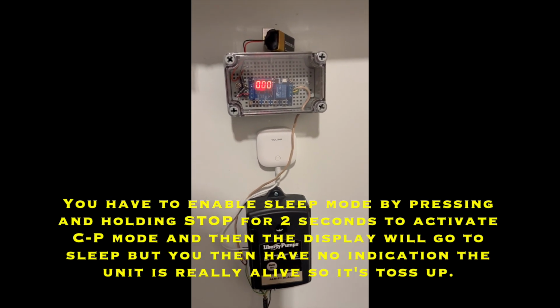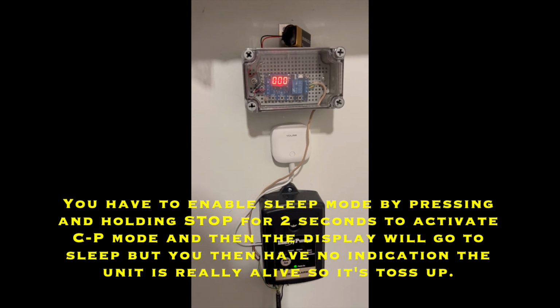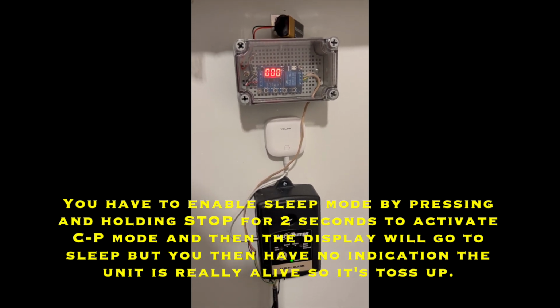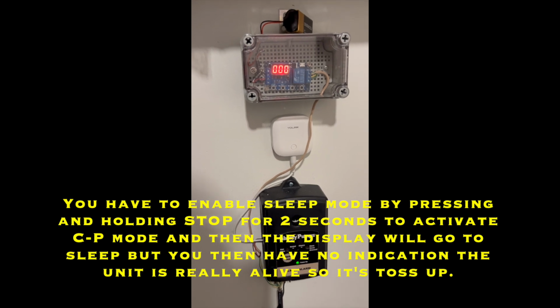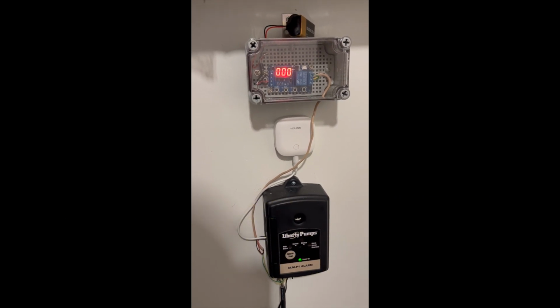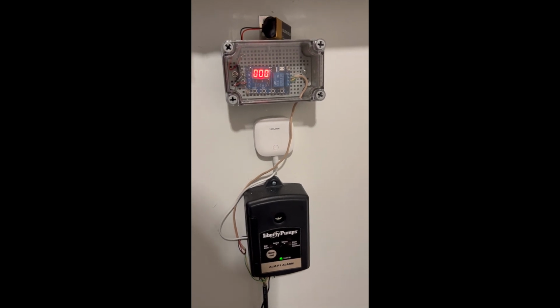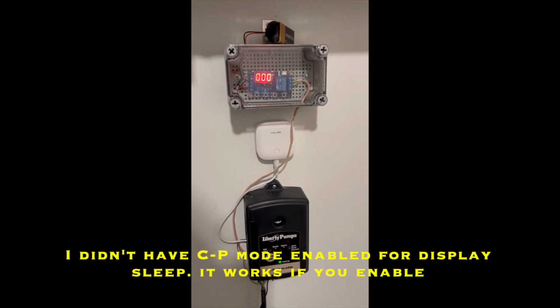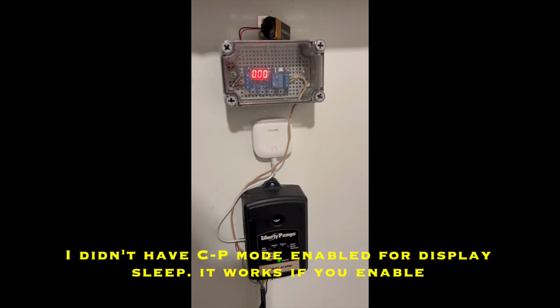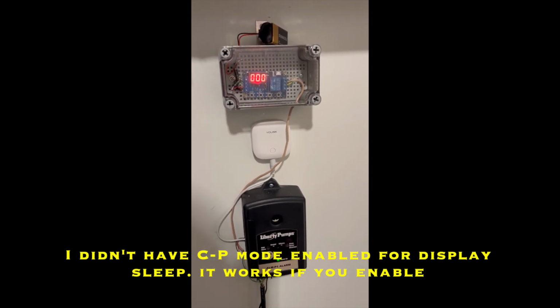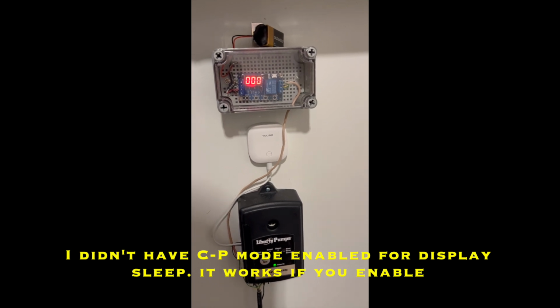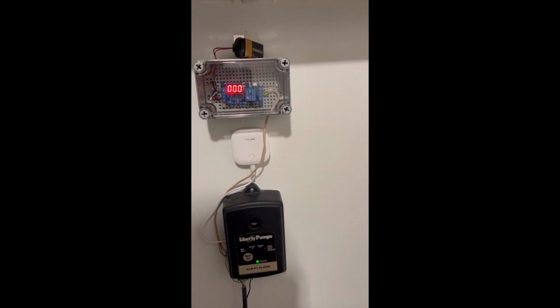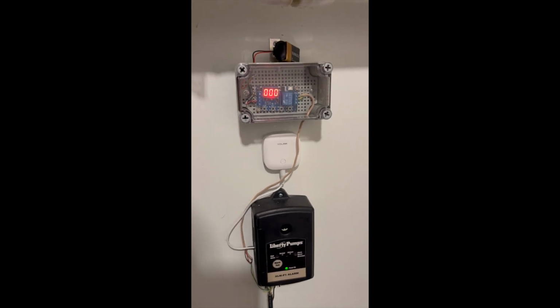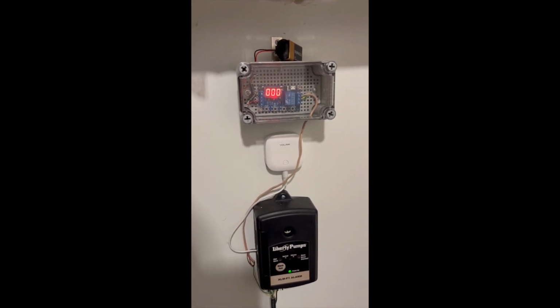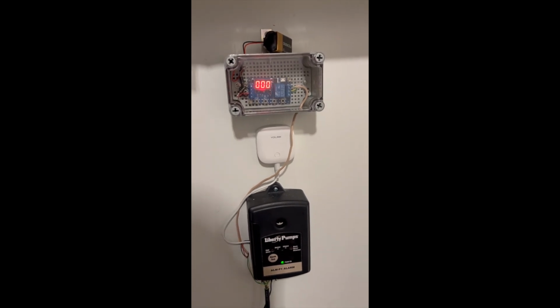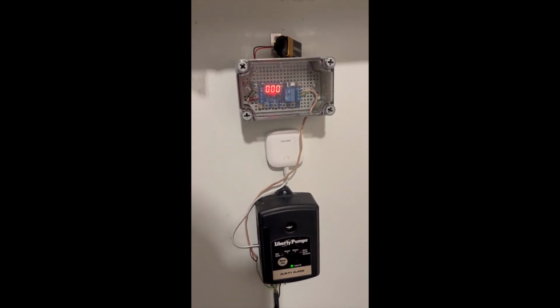The display, I don't think, is going to go off after 5 minutes like the manual says. Supposedly after 5 minutes of the relay being inactive, the display will go off. I haven't seen it happen yet. It could have something to do with the fact that we reversed the logic using the F2 function by holding the down key. That allows us to keep the same program as before, P4, but now use the normally open contacts instead of the normally closed contacts. So now our normal mode is that the relay is de-energized, and in an alarm condition we energize the relay to close the normally open contacts.